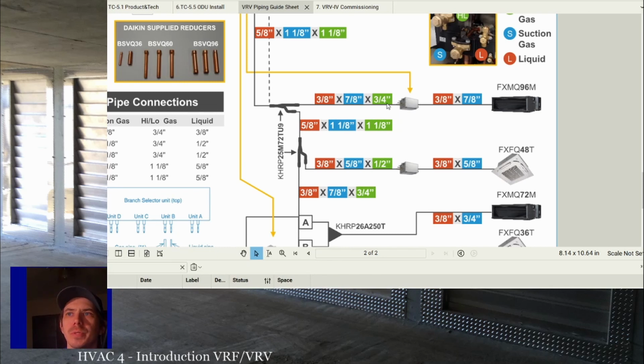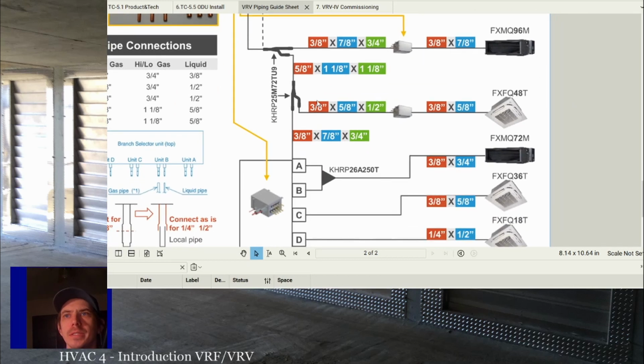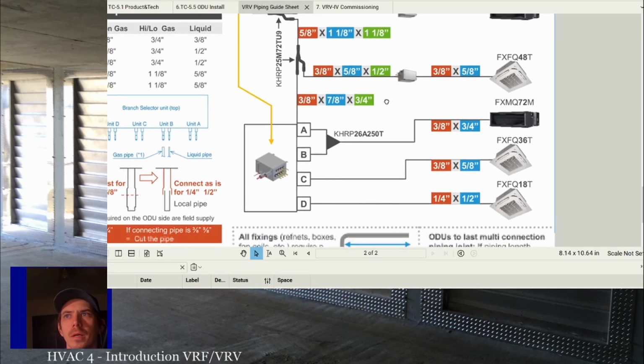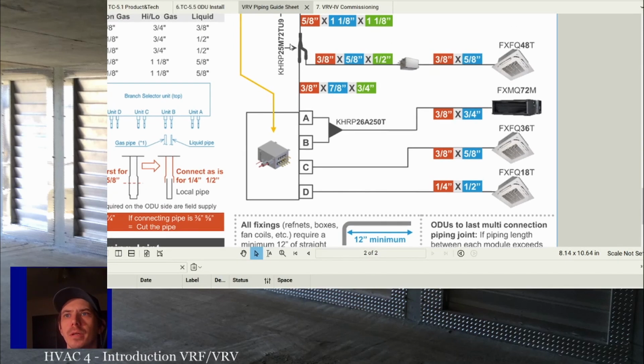And then this splits off to a single branch selector that serves a single unit. And you can see there's only two lines that go to the indoor unit. So three lines split, serve the rest of the units. This one splits to serve a single unit. Same thing here. The line splits again. So all three lines split. Then you have the three lines go to this branch selector, goes to a single indoor unit. Then this splits down here, goes into a multi-port branch selector, and goes to individual units.